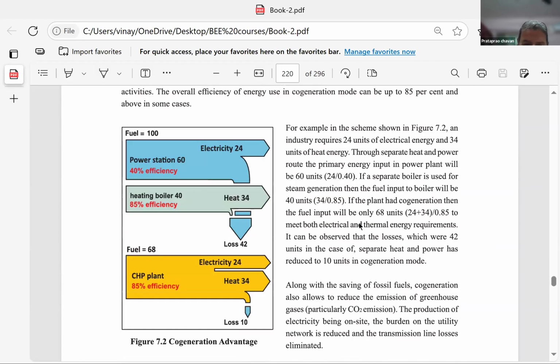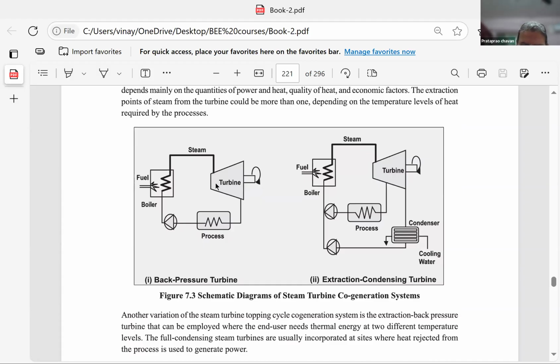Now here, what we are doing is not allowing it to be exhausted into the condenser. Some pressure and temperature of the steam is extracted, goes to the process and then goes to the boiler. Right, this is one way. Back pressure: here is a little modification in this system. In this system, there is no exhaust or condenser. Here we want to get the benefit of both these systems. That means we are partially giving steam to the process and partially allowing it to exhaust into the condenser. Here the efficiency may be more.